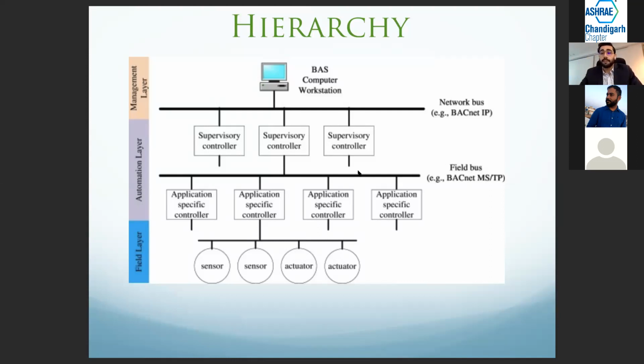Typically, if there's any construction going on, for example, and some contractor comes in and cuts the wire because they didn't pay attention to what was going to happen to the controls, you're going to lose your link where the wire's cut, and you're not going to be able to see anything else on that link moving forward. So then we need to go and fix the wire and bring the link back up. Physically, the sensors, actuators, and all the other stuff land on the unit level controller, and then unit level controllers are all daisy chained together, as we just discussed.